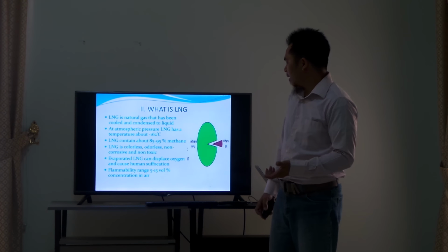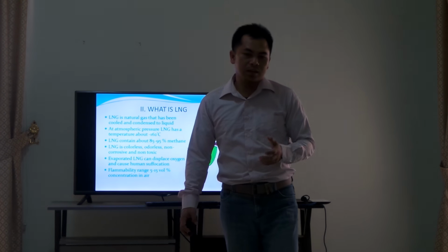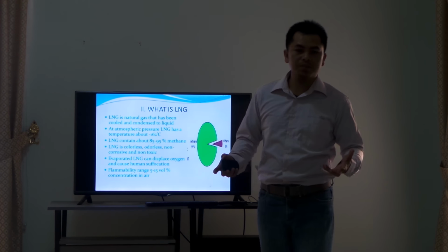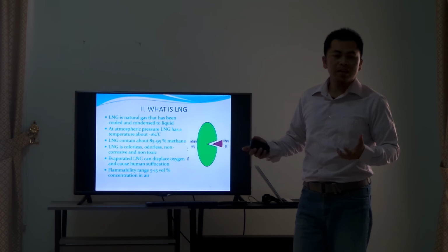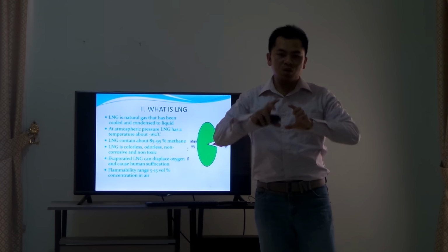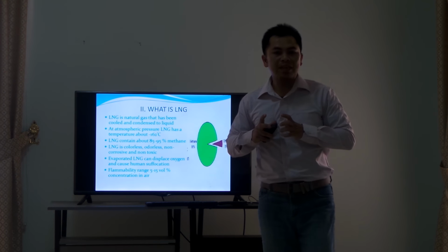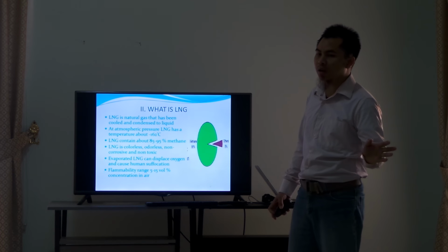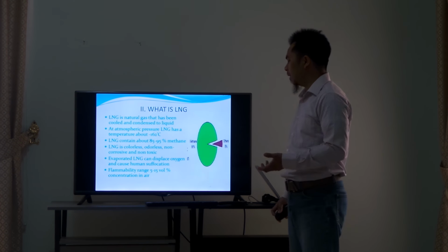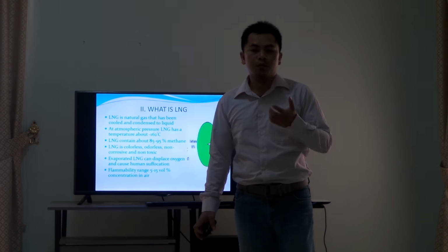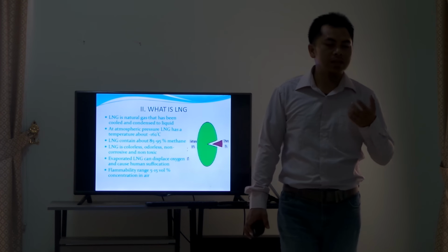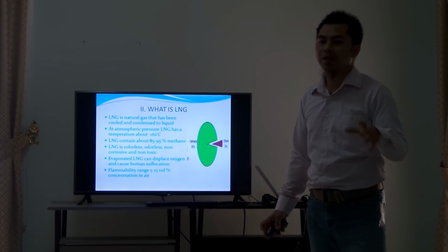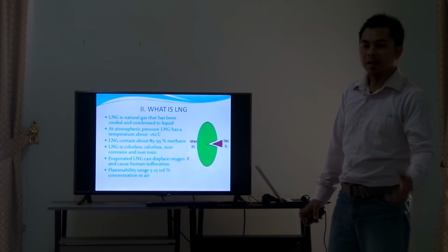Evaporated LNG can displace oxygen and cause human asphyxiation. If the concentration of LNG in this room, for example, gets high enough, it can displace the oxygen that we use for breathing. That's why it can cause suffocation for humans. This is one of the hazards of LNG. And then the flammability range is 5 to 15% volume in air. Flammability means there is a possibility of fire or explosion if the concentration of LNG is 5 to 15% in air.